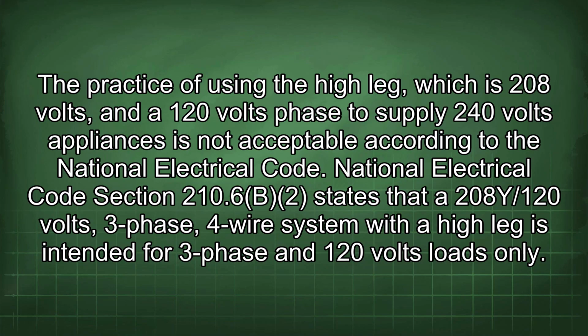The practice of using the high leg, which is 208 volts, and a 120 volts phase to supply 240 volts appliances is not acceptable according to the National Electrical Code. National Electrical Code Section 210.6 B2 states that a 208Y/120 volts, 3-phase, 4-wire system with a high leg is intended for 3-phase and 120 volts loads only.